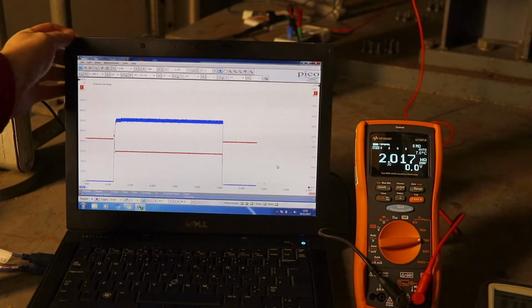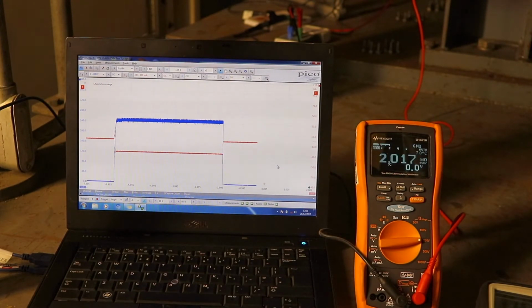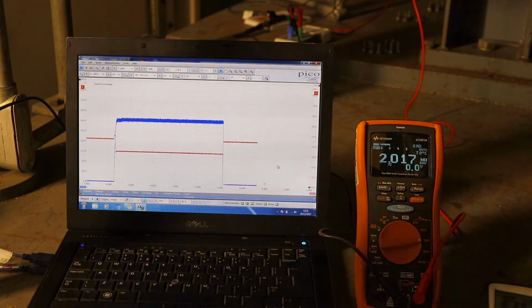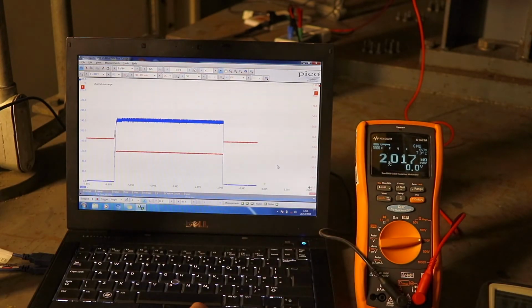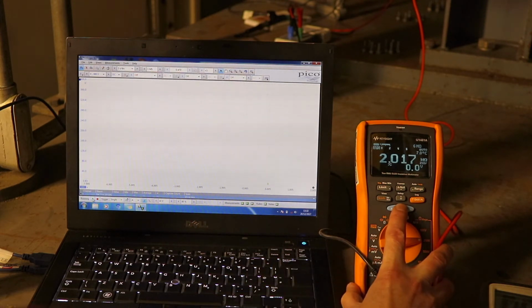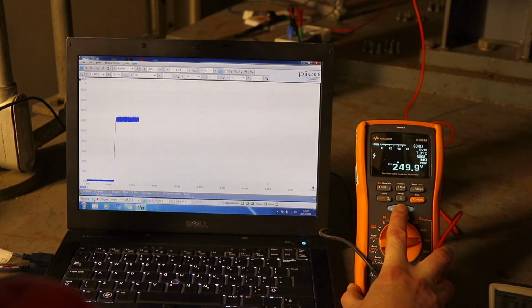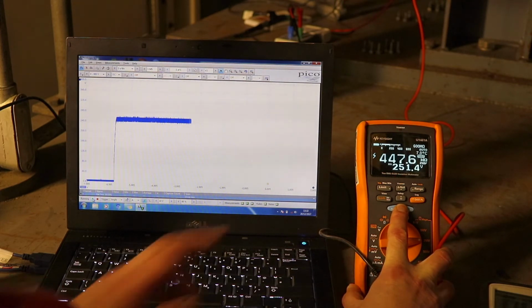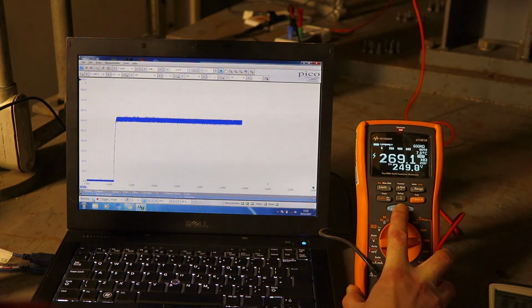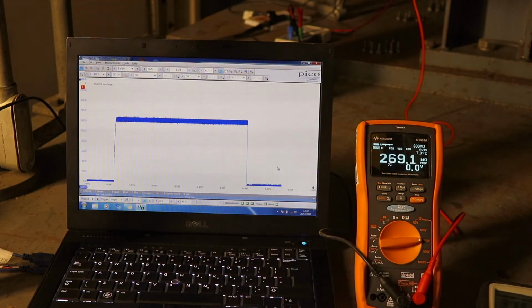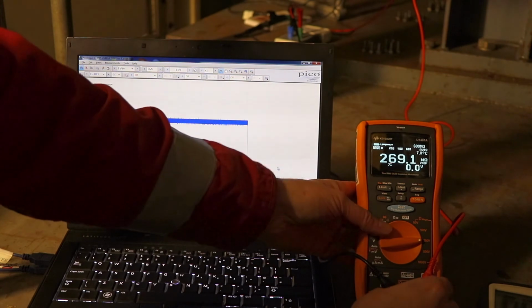Okay, so the current has been completely removed from the test setup. I'm just measuring the voltage output of the insulation tester, so we'll repeat the tests. With that, we'll turn channel B off. Put you on. See the voltage, and you see the reading starts to go erratic again with the Keysight unit. So 269 megohms on that occasion.